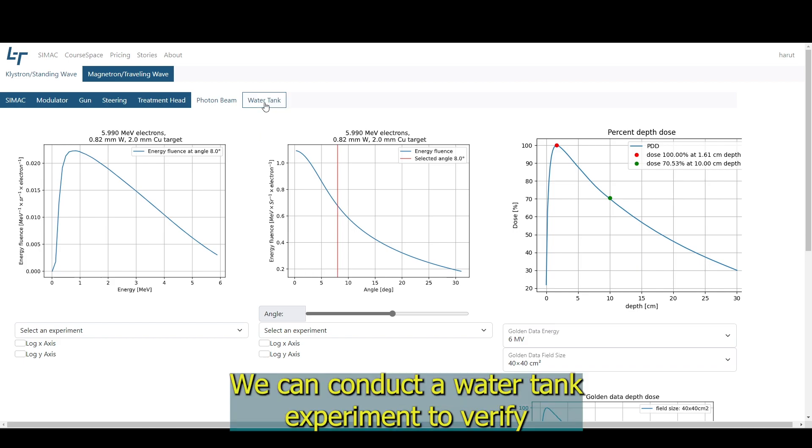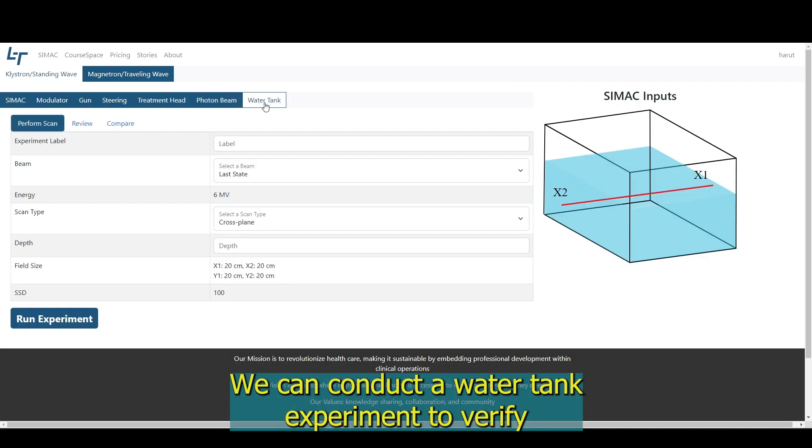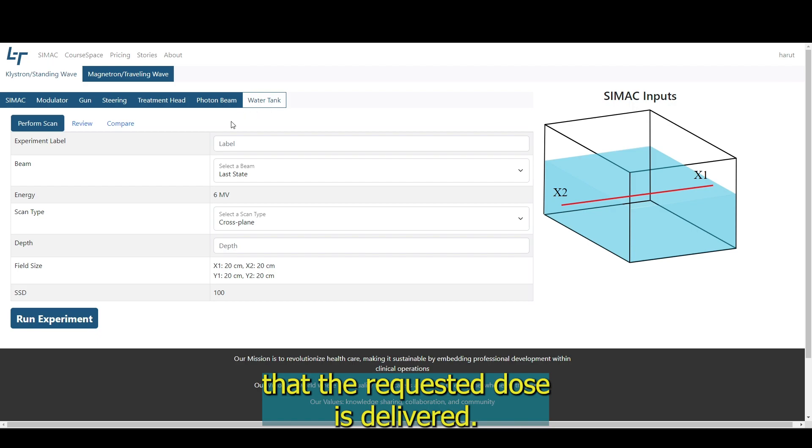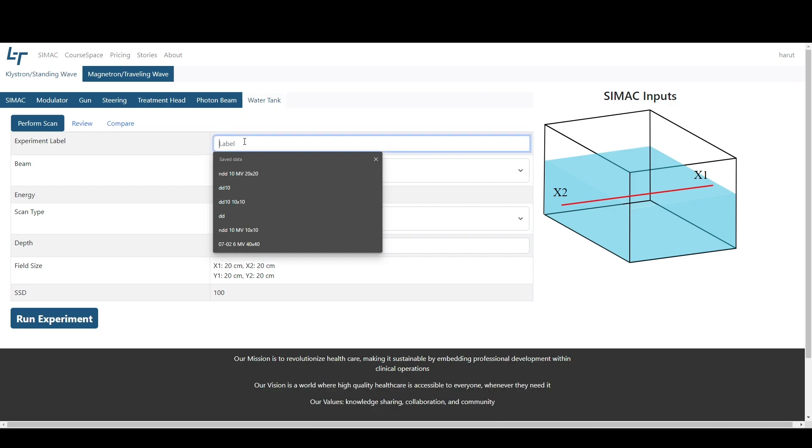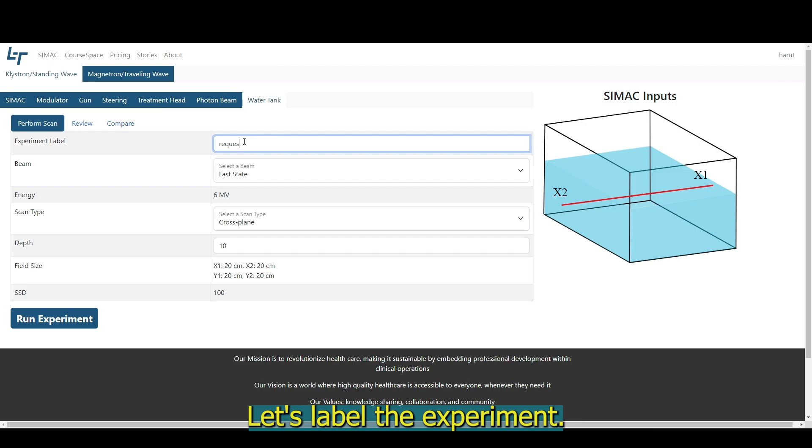In the water tank tab, we can conduct a water tank experiment to verify that the requested dose is delivered. Let's label the experiment.